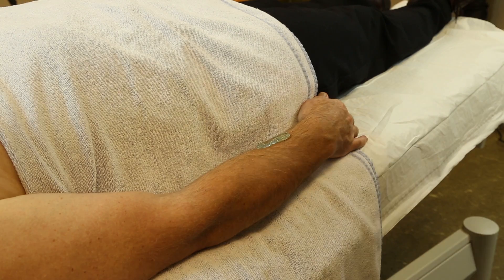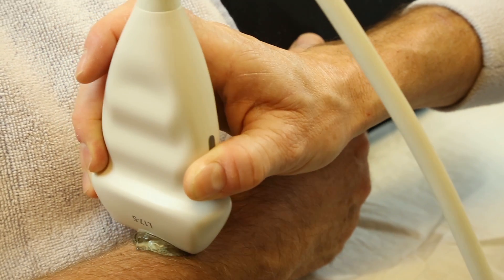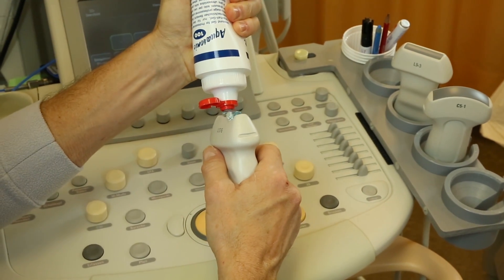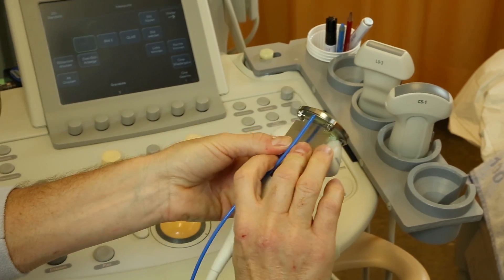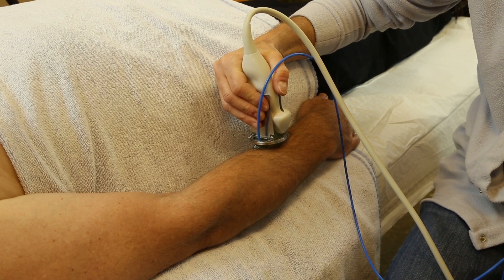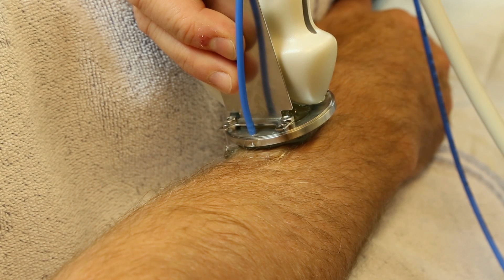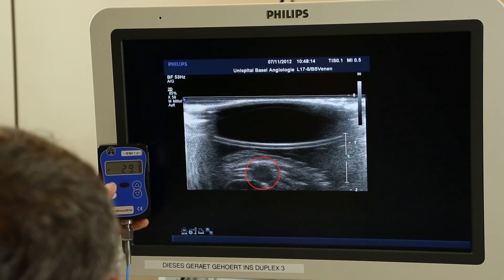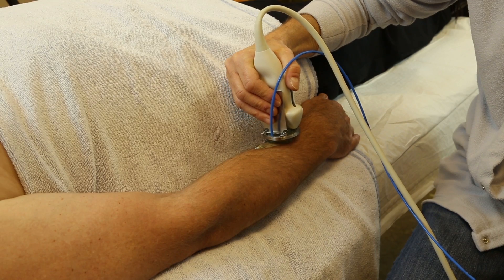The sonographer is looking for a suitable vein on the forearm. The vein is displayed in cross-section. Best results are achieved when the vein is situated directly above a bone. The pressure device is now connected to an ultrasound transducer. The vein is displayed and slowly compressed. The system is being leveled — make sure that the elastic membrane at the front of the device has no skin contact.